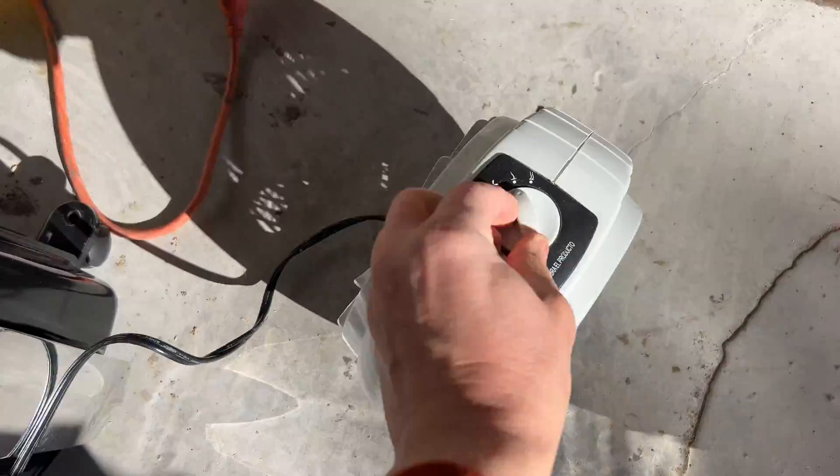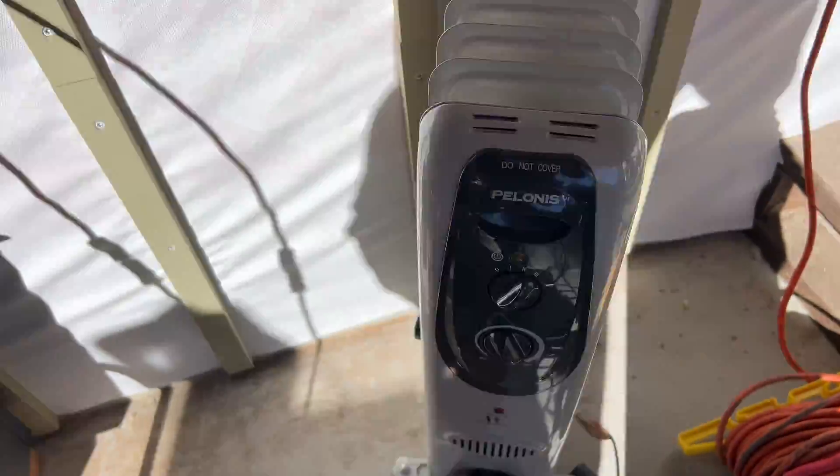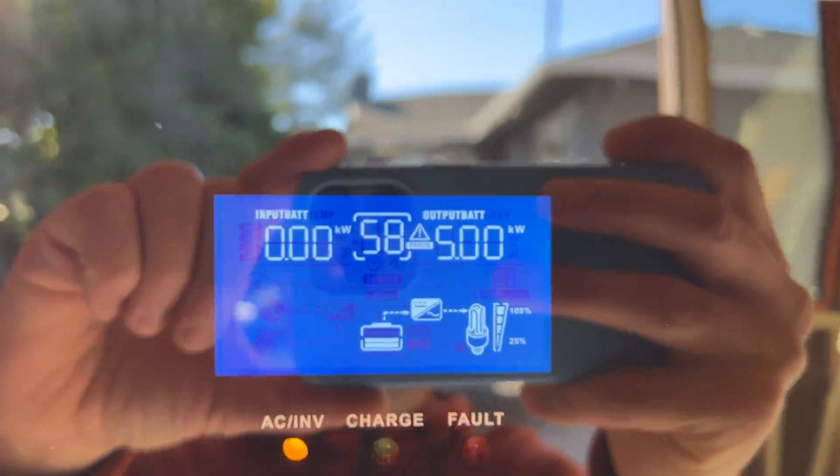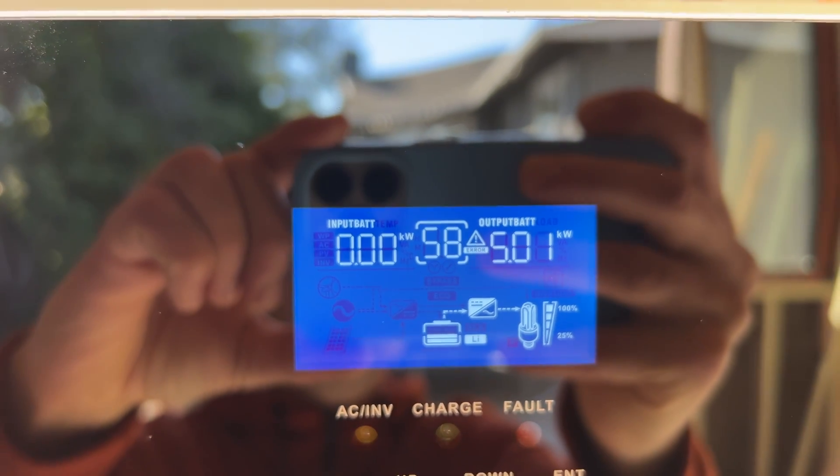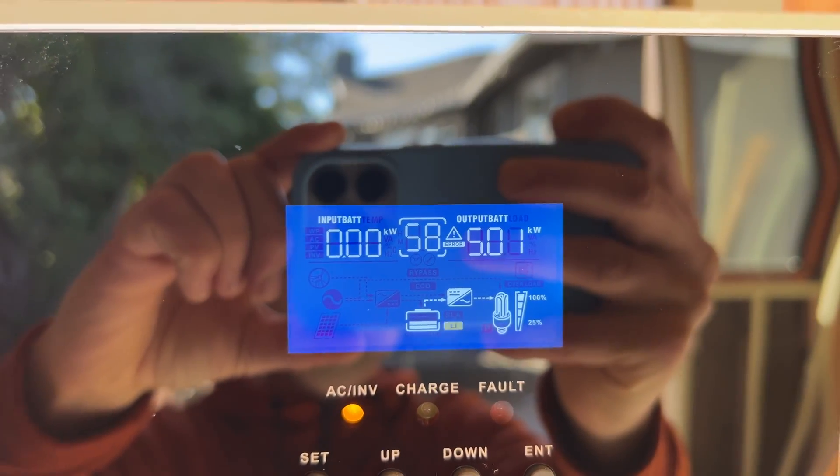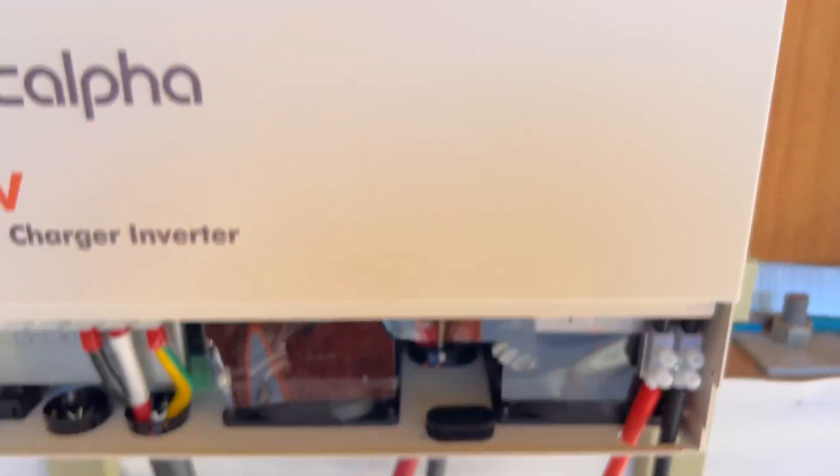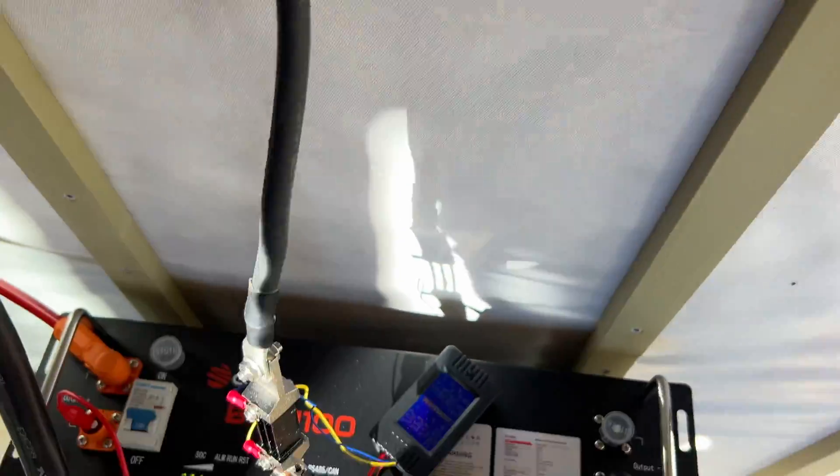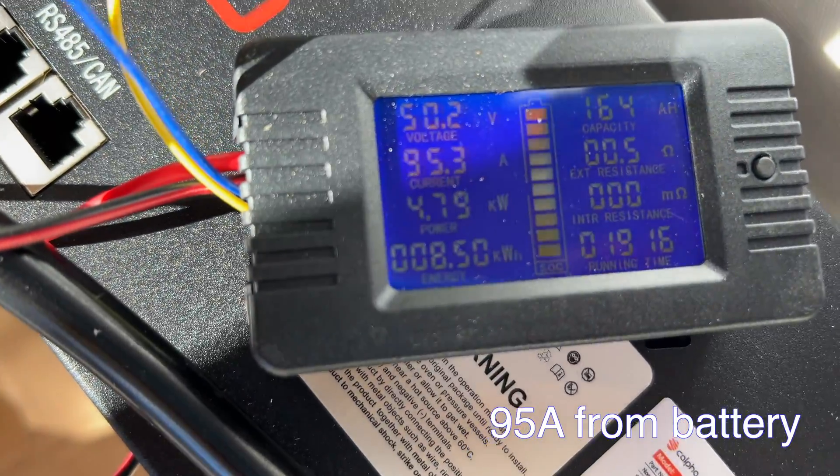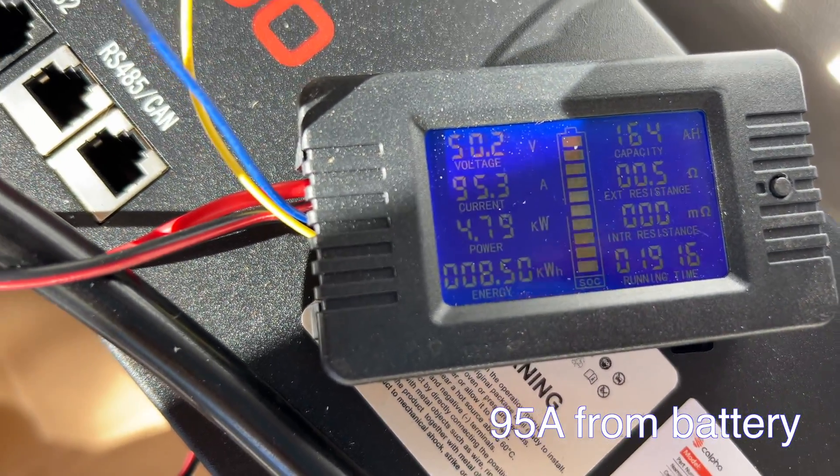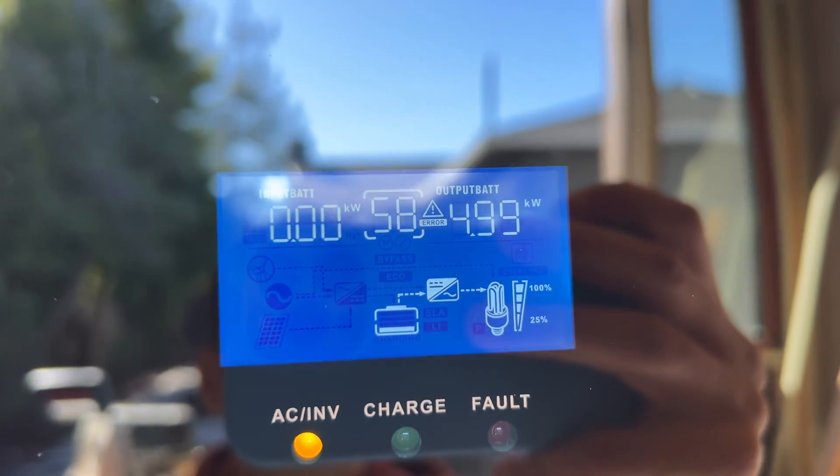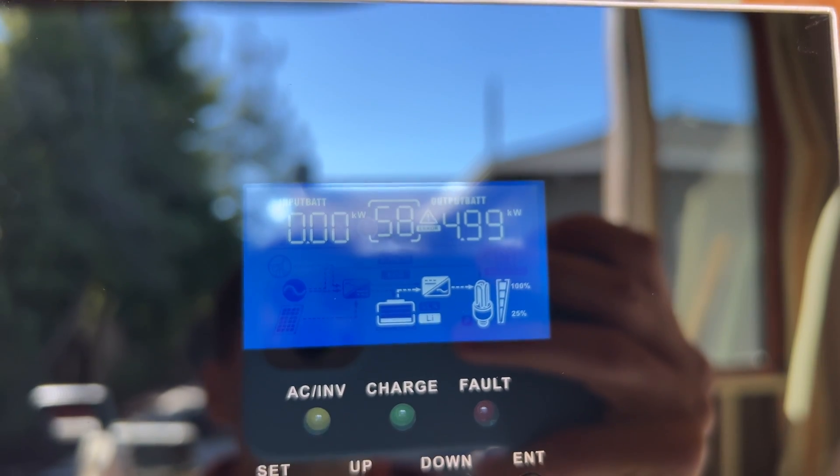For the load test, I'm going to use space heaters, 1.6 kilowatts each heater. And I draw exactly 5 kilowatts, which is maximum load for inverter. Test was running for about 10 minutes and the inverter and battery didn't shut down.